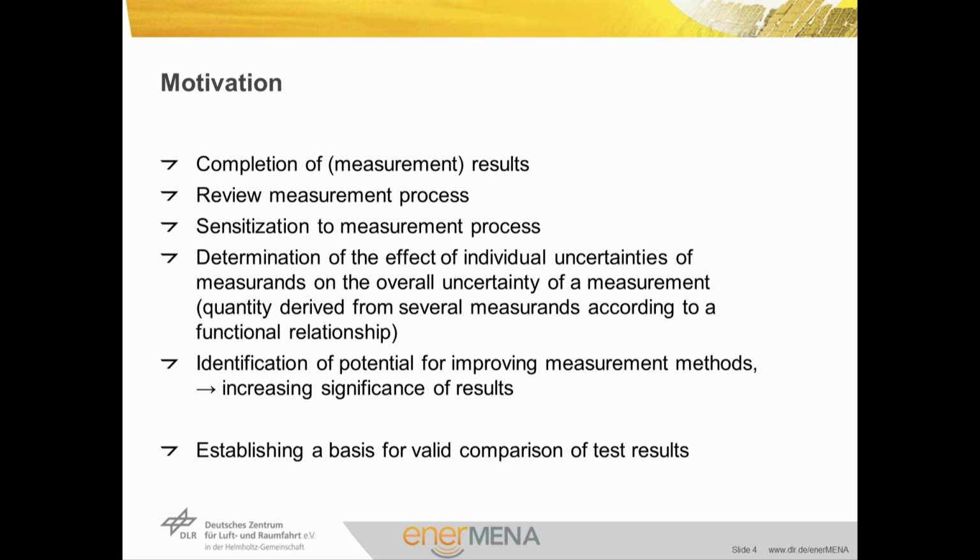any test data evaluation. Most importantly, the uncertainty of a test result determines its significance. What does this mean? A measurement reading or result as such is essentially a random guess of the measurand. It does not contain any information on how likely the value is to represent the actual measurand. In other words, you do not know how good or bad the value is unless you know the width of the associated uncertainty band. Consequently, reliable values of uncertainty are absolutely necessary for the assessment and comparison of test results.